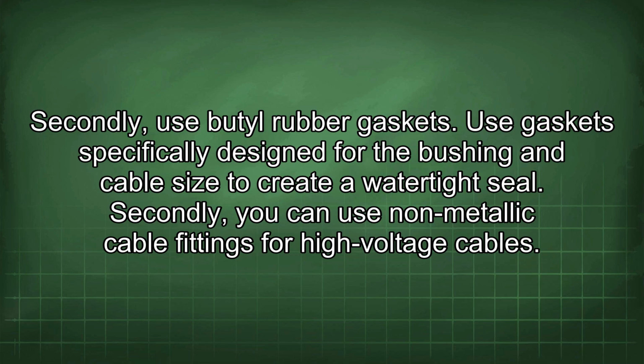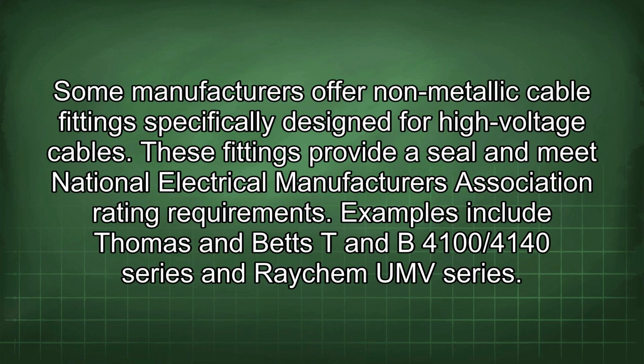Secondly, you can use non-metallic cable fittings for high-voltage cables. Some manufacturers offer non-metallic cable fittings specifically designed for high-voltage cables. These fittings provide a seal and meet National Electrical Manufacturers Association rating requirements. Examples include Thomas and Betts T and B 4100/4140 series and Raychem UMV series.